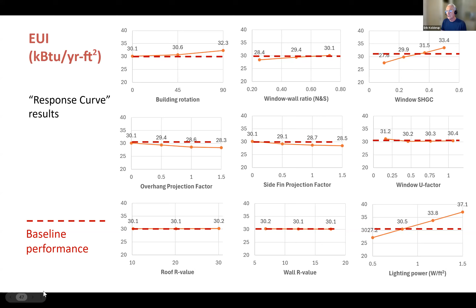EUI is definitely important, but there are other things to consider. Say, for example, you're interested in HVAC sizing impacts - some measures might have a bigger impact on loads than on energy consumption. You can see that having a building rotation with big east and west facing glass has a big impact on the peak load of the cooling system, which is a cost for the building for sure.